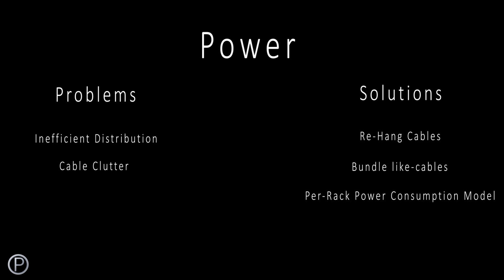Ignoring the amount of floor space, Stevens Hall could use a per rack power consumption model to record exactly how much power is coming from each rack. A handful of servers can be put in each rack, leaving the rest of the rack empty. This would create a lower power density in each rack. Using the detection of how much power there is per rack, Stevens Hall can distribute power accordingly.